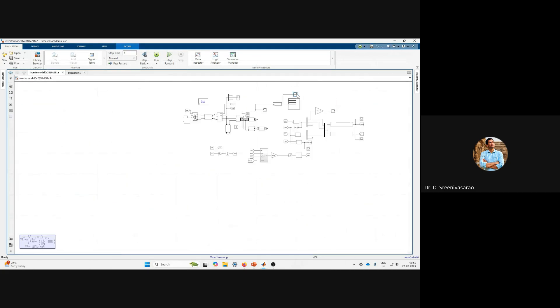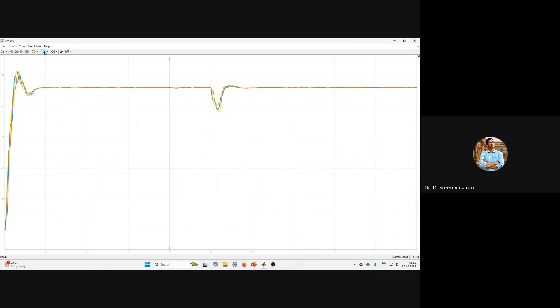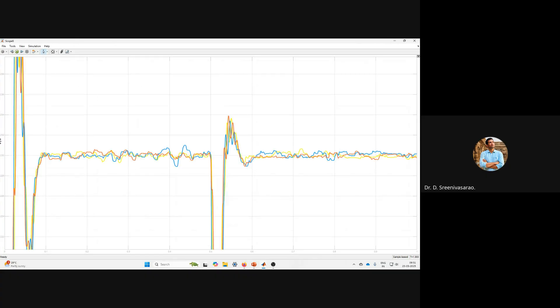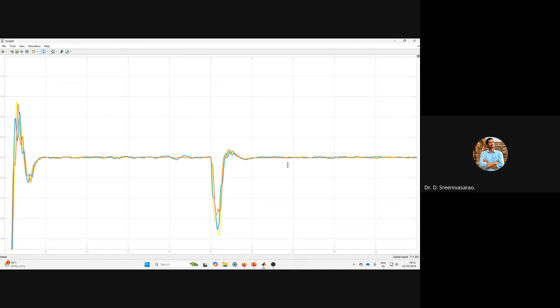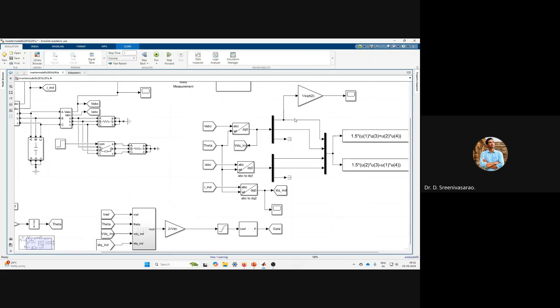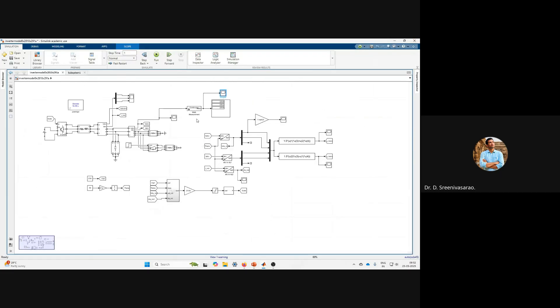The RMS values are 230 volts phase voltage. When the load is increased there is a small reduction in RMS value, but the controller stabilizes and restores the reference. When load is removed, there is a slight rise in voltage for a short duration. This demonstrates grid-forming inverter operation using multi-loop droop control.